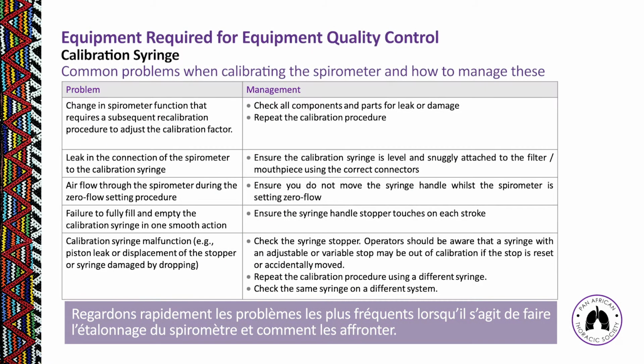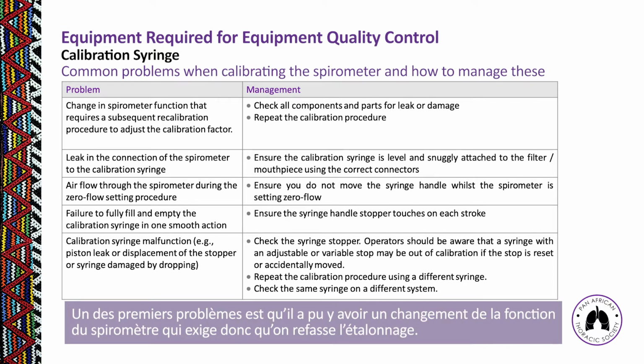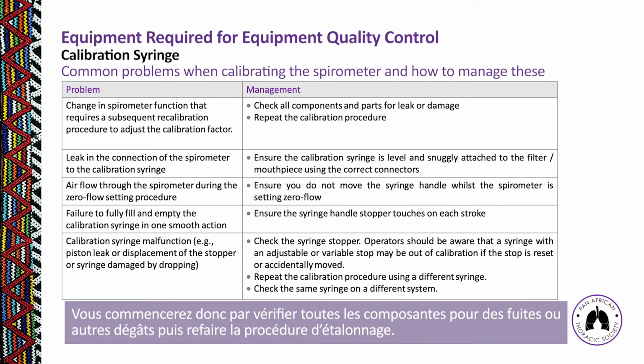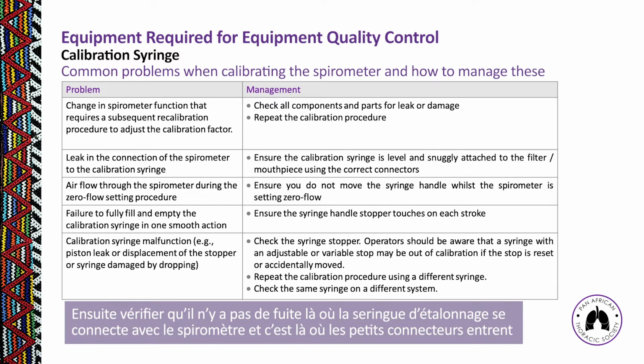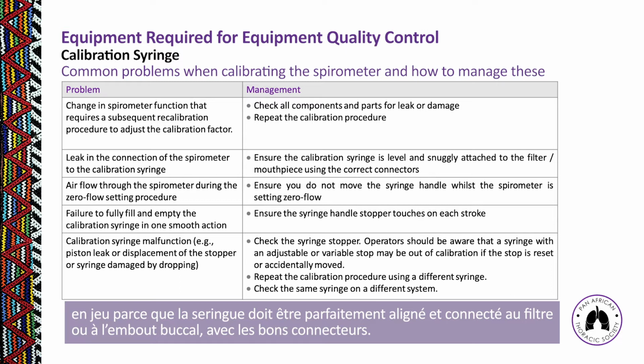Let's look quickly at the common problems when calibrating the spirometer and how to manage these. One of the first things is that there could be a change in the spirometer function that requires a subsequent recalibration procedure to adjust the calibration factor. What you should do is check all the components and parts for leak or damage, and then repeat the calibration procedure again. Next, look for a leak in the connection of the spirometer to the calibration syringe, and that's where all these little connectors become important, because we want to make sure that the syringe is level and snugly attached to the filter or mouthpiece using the correct connectors.